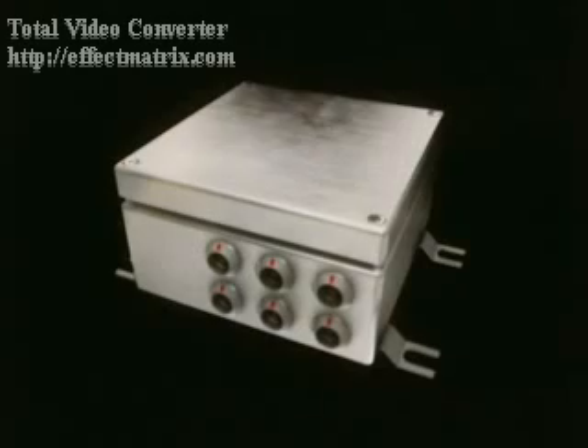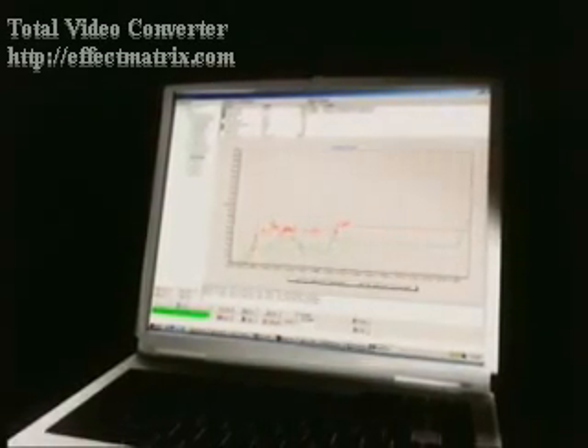Today, 2 channels are used for measuring loads and 3 channels for measuring temperatures. The other 3 channels are reserved for future use. The BHE unit consists of a microchip, a flash memory, and an AD converter. All the startup calibration data, together with the ID of the unit, is stored in the flash memory, making it traceable with all the data retained at any given time.